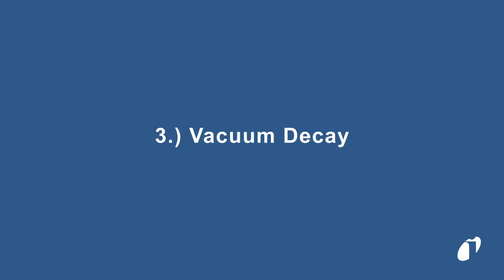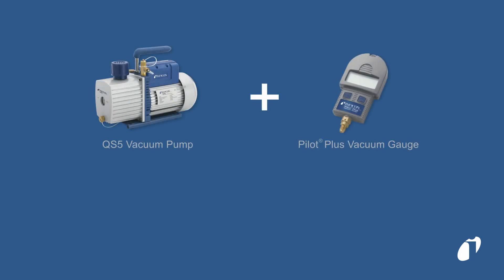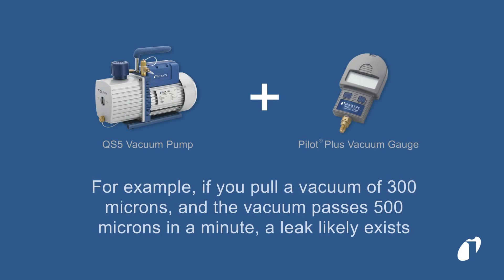Observing vacuum decay is a quick, non-destructive way to gauge the tightness of your system. Pull a vacuum on the system and observe the system pressure. If the system pressure rises by a significant amount in a short amount of time, that is a good indication that there is a leak or multiple leaks somewhere in the system.